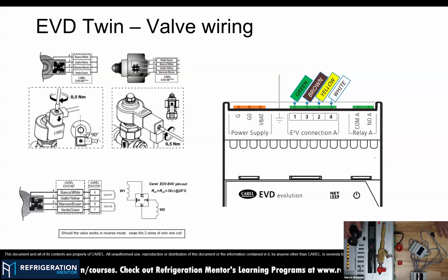And this is one of the main points of failure in the field, Trevor. I was talking to you before. I've been to this transcritical site last year, and I asked the people there, everything is right, is wired, it's working. Yeah, no problem. Then I start playing with the parameters because the rack was not responding. And when we checked it, we had a splice in the middle of the way and the cables were reversed. So when the valve was asked to open, in fact, it was closing and the opposite. So we never found a good regulation point.